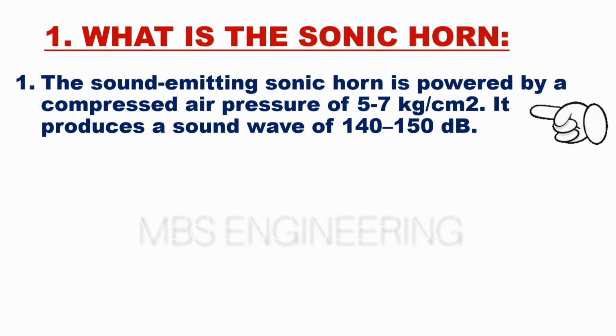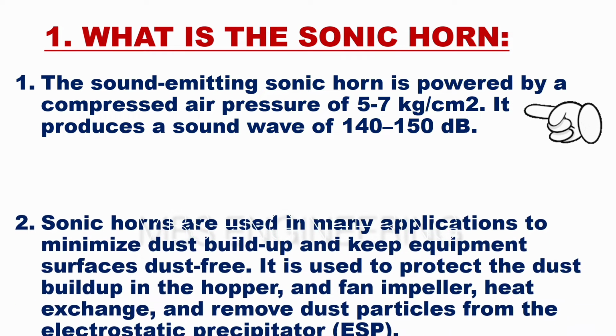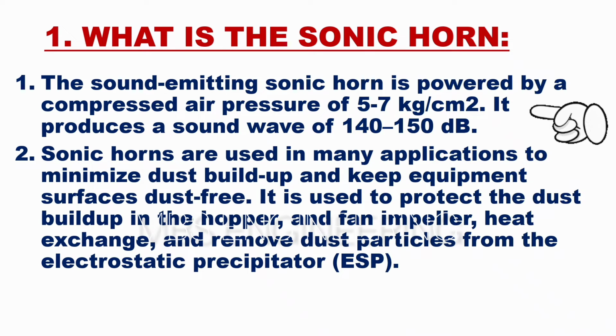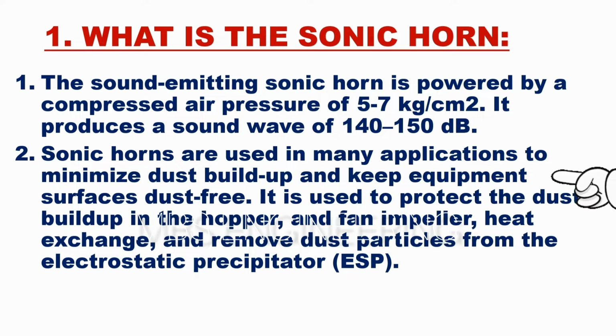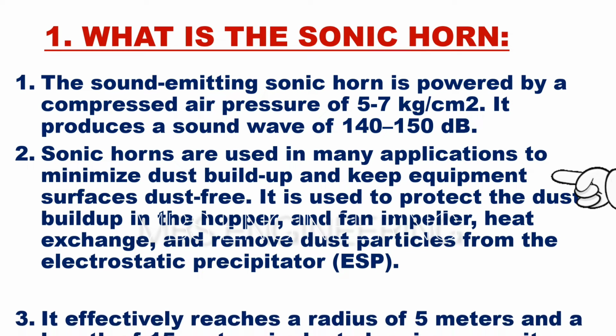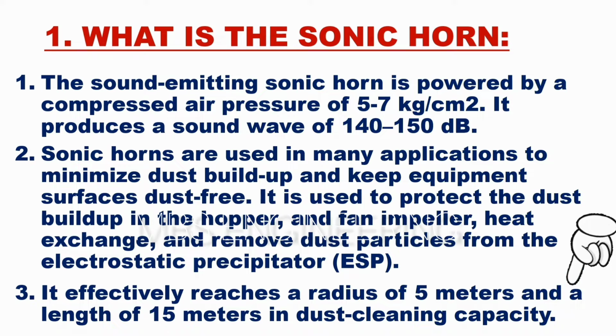Next, we learn about what is the sonic horn. The first point, the sound-emitting sonic horn is powered by a compressed air pressure of 5 to 7 kilograms per centimeter square. It produces a sound wave of 140 to 150 decibels. The second topic is, the sonic horns are used in many applications to minimize dust buildup and keep equipment surfaces dust-free. It is used to protect the dust buildup in the hopper and fan impeller, heat exchangers, and remove dust particles from the electrostatic precipitator ESP. The third point effectively reaches up to a radius of 5 meters and a length of 15 meters in dust cleaning capacity.